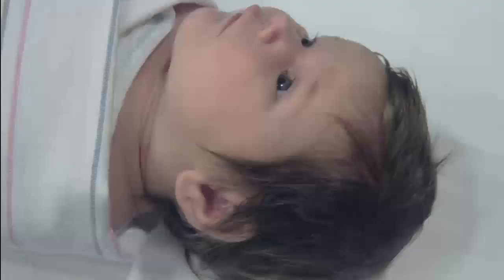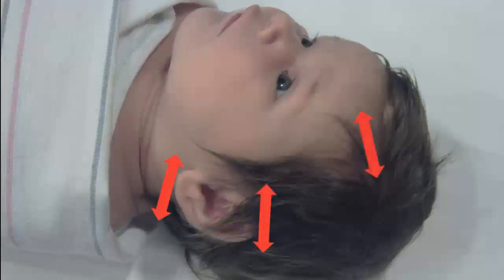The BERAphone electrodes make contact with the baby's head at 3 locations. One is just below or behind the earlobe. This is referred to as the mastoid electrode. One electrode lays just above the ear. This is the ground electrode. The vertex electrode lays on the forehead at the hairline.